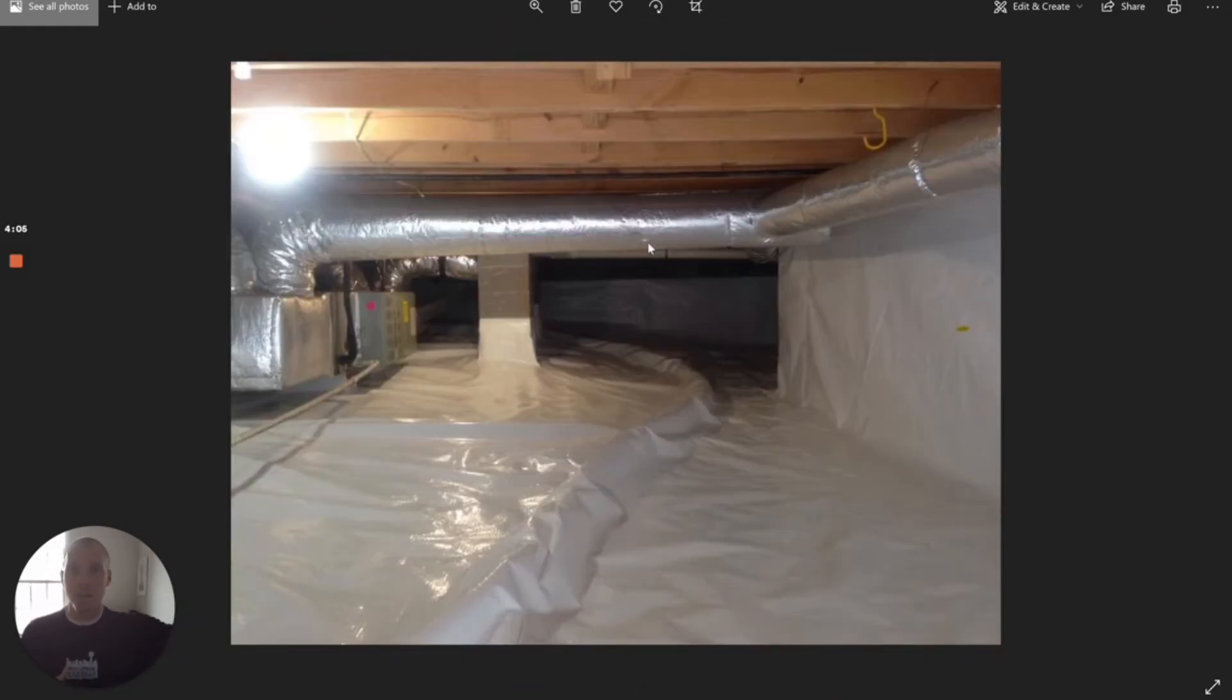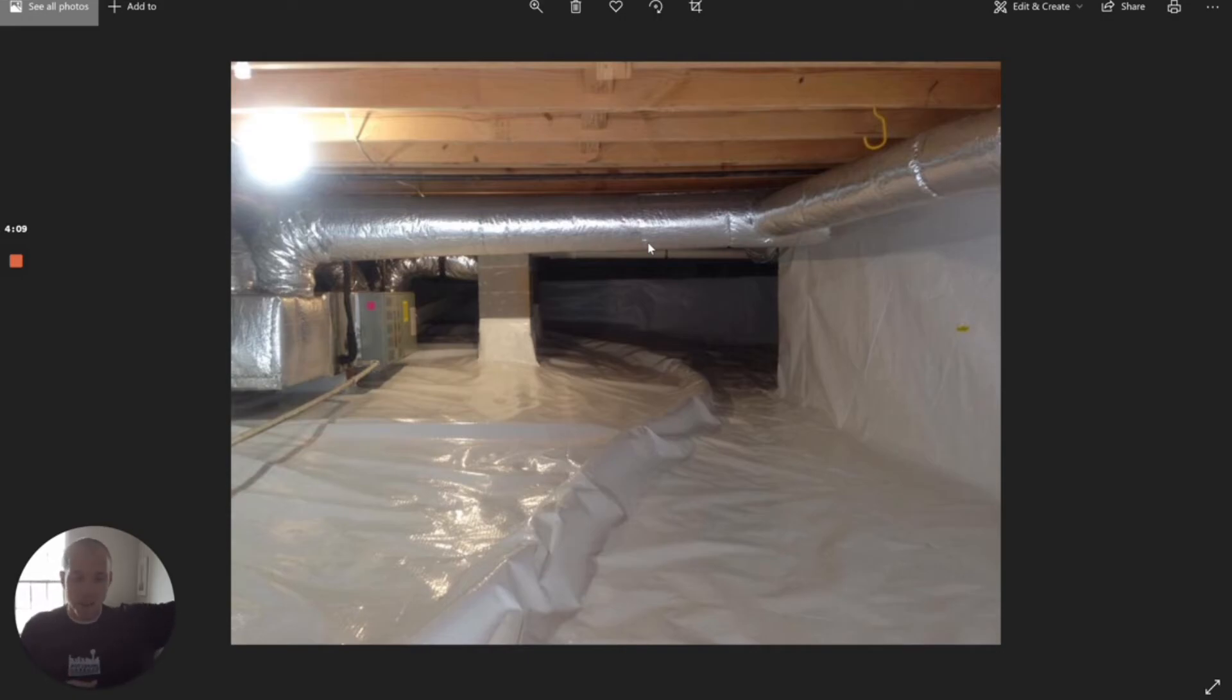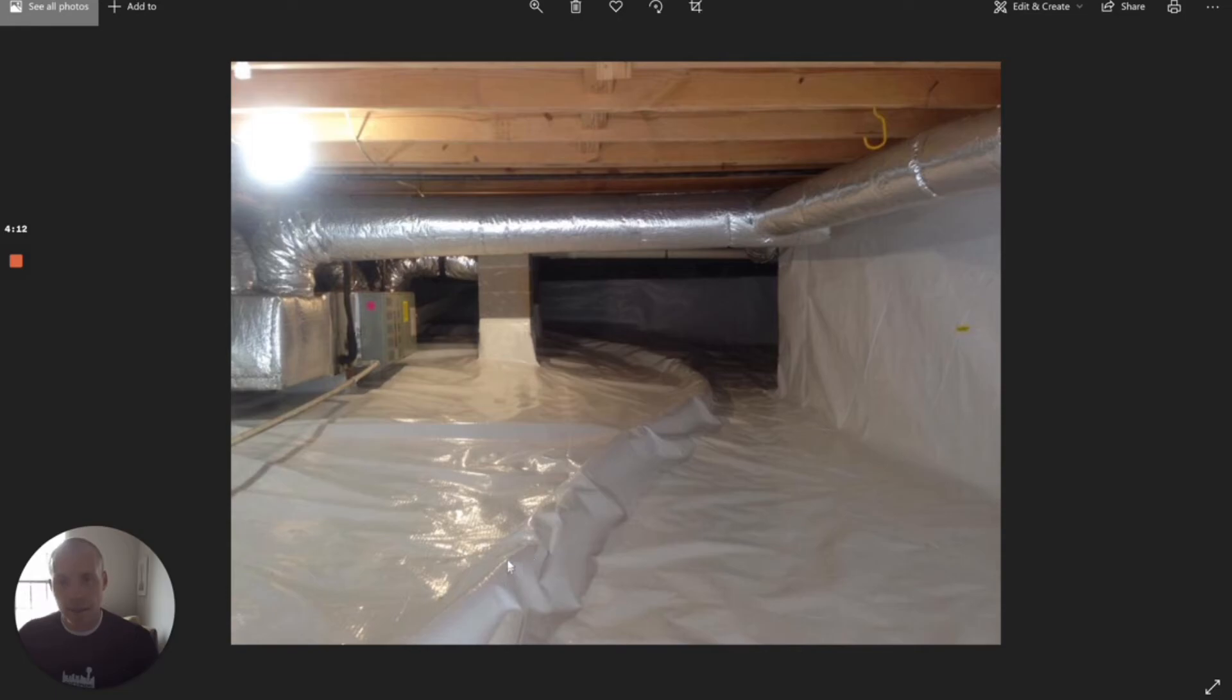That's when you come in and you install that same system—the radon vent pipe and fan—and then you extend that pipe and you run it underneath the plastic, like this right here. That's what this pipe is running through this crawl space. Notice the edges of the vapor barrier are sealed; they took this one and ran it up the wall.